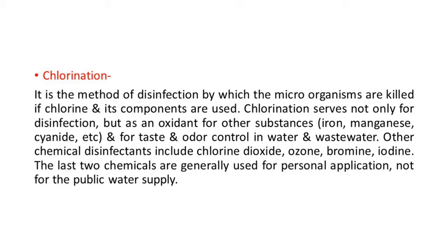The third form, and the most used, is called free chlorine gas. Chlorine is applied in the form of gas, either by mixing the gas in a small quantity of water and then giving the solution to the water which is to be treated, or by converting gas into liquid by applying pressure of about 0.7 Newton per mm square, and the water is disinfected.